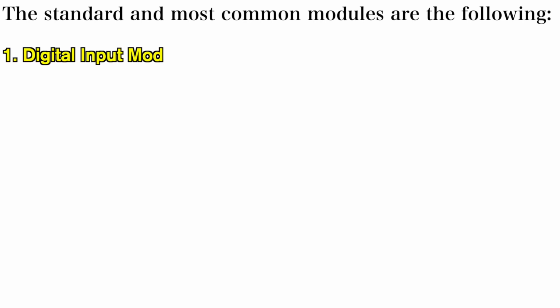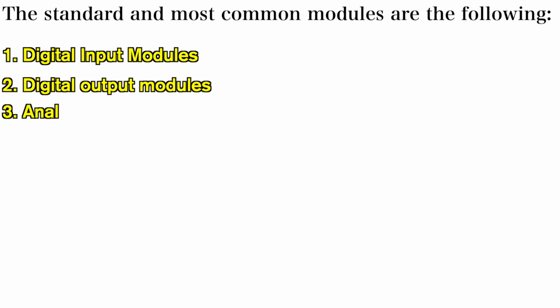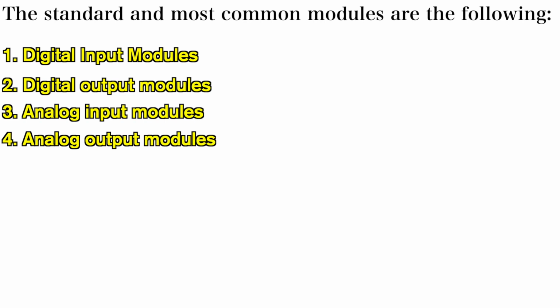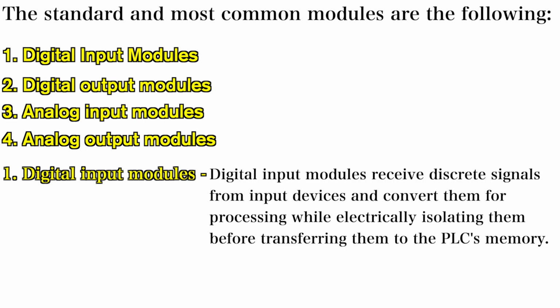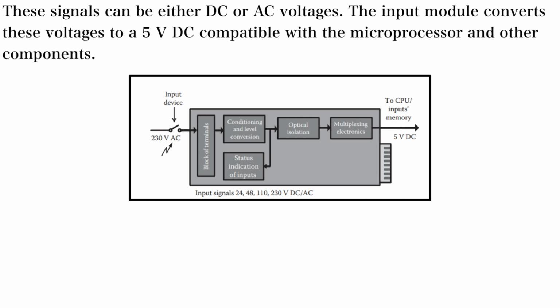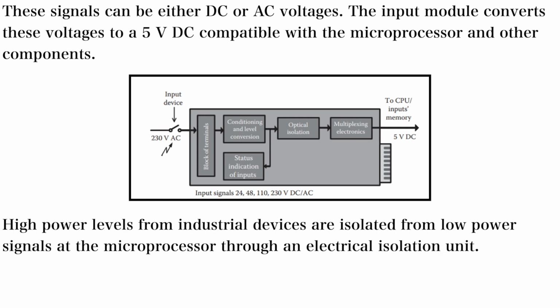First is the digital input modules, second the digital output modules, third the analog input modules and fourth the analog output modules. First let's give an explanation about the digital input module. The digital input modules receive discrete signals from input devices and mainly convert them for processing while electrically isolating them before transferring them to the PLC memory. Next, this discrete signal can be either AC or DC voltage. The input module mainly converts these voltages to 5 volt DC, which is compatible with the microprocessor and the other components. The high power levels from the industrial devices are isolated from the low power signals at the microprocessor through an electrical isolation unit, which is mainly for the safety of our systems or the components of our industry.